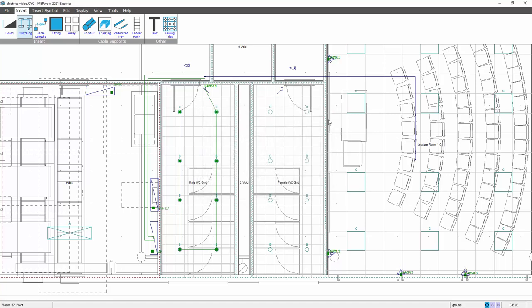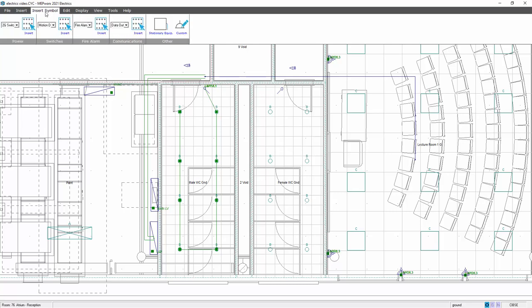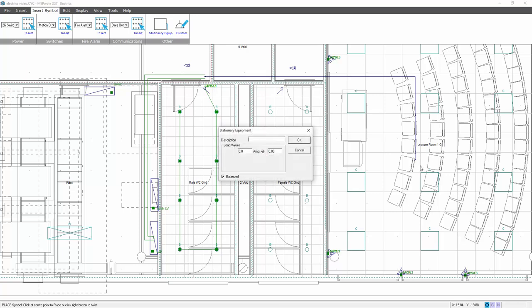So for example, if I was to put a fan coil unit in this lecture room here, I would use the stationary equipment option, and perhaps I might run it from the HVAC board. So what I would do this time, I would select the HVAC board. First of all, I need to put the symbol in to represent the load. If I insert symbol and select stationary equipment, I then place the stationary equipment load, give it a description, other AC systems are available, and I'll make that a 20 amp load.